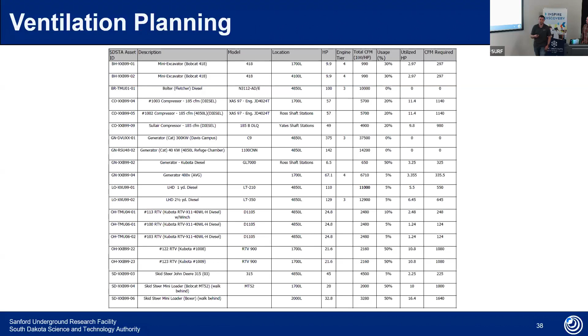So what we do is go through and assign a usage, a utilization factor, giving it a percent of time that it's going to be up and running. No piece of equipment underground runs 100% of the time, so that's where that comes into play. Then we can break down what rated horsepower is being used throughout the year and give it a better number for the CFM requirement. That's where we got that 86 diesel horsepower for our equipment.